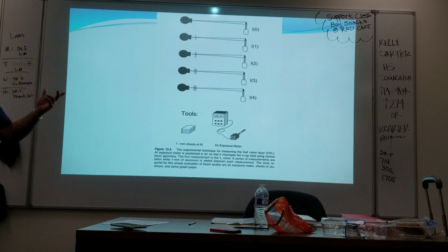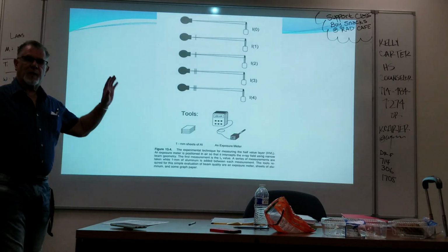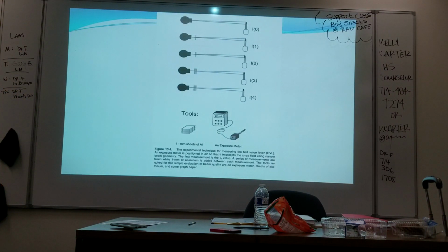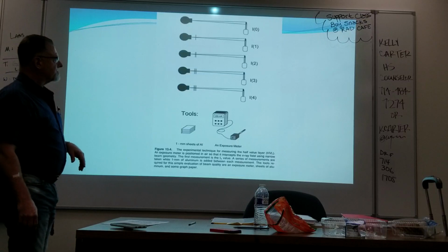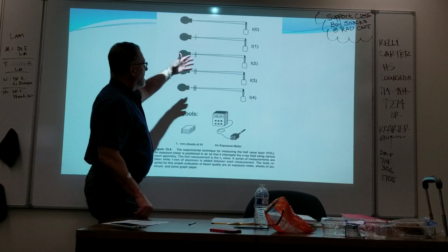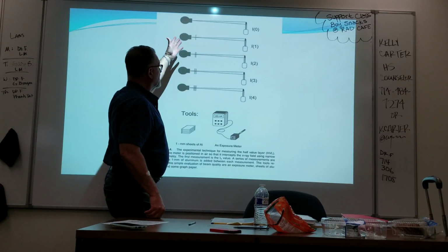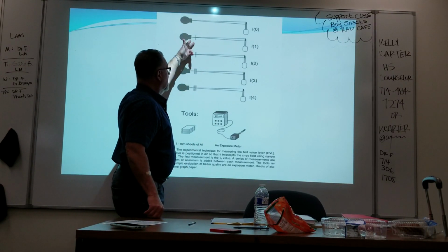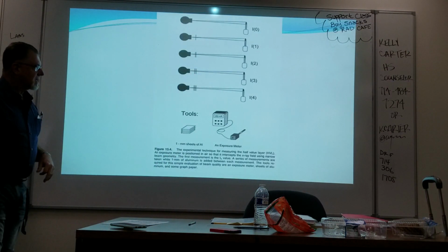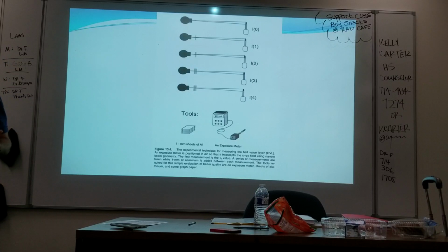This is especially important for mammography. It's a required test that the feds require if you're going to be certified to do mammo. Half-value layer is another important test. That's really kind of easy. You just start out with a detector and a standard exposure, and you keep adding successive amounts of aluminum in this case, and you can determine what the half-value layer is for the X-ray.